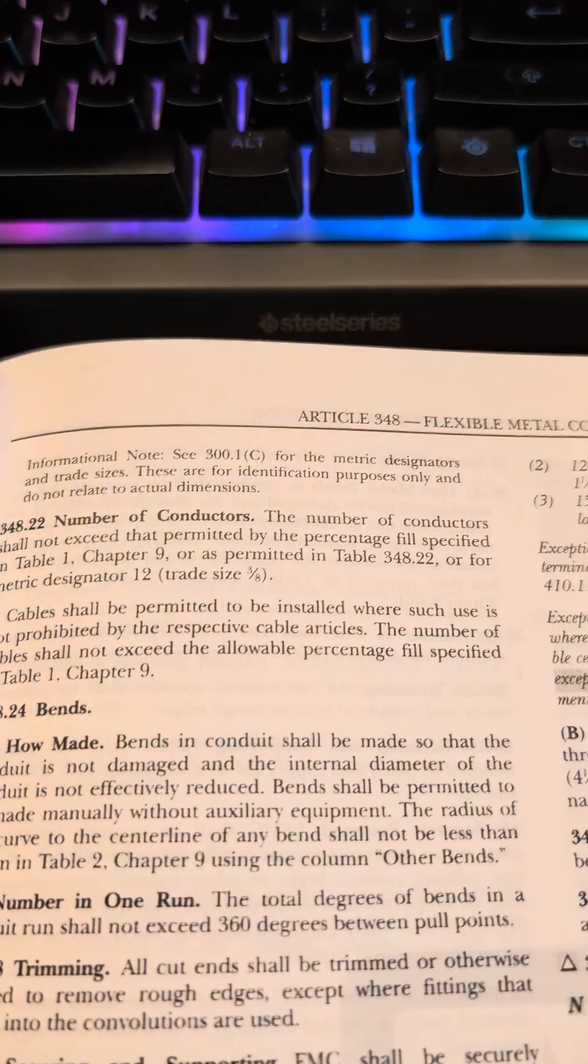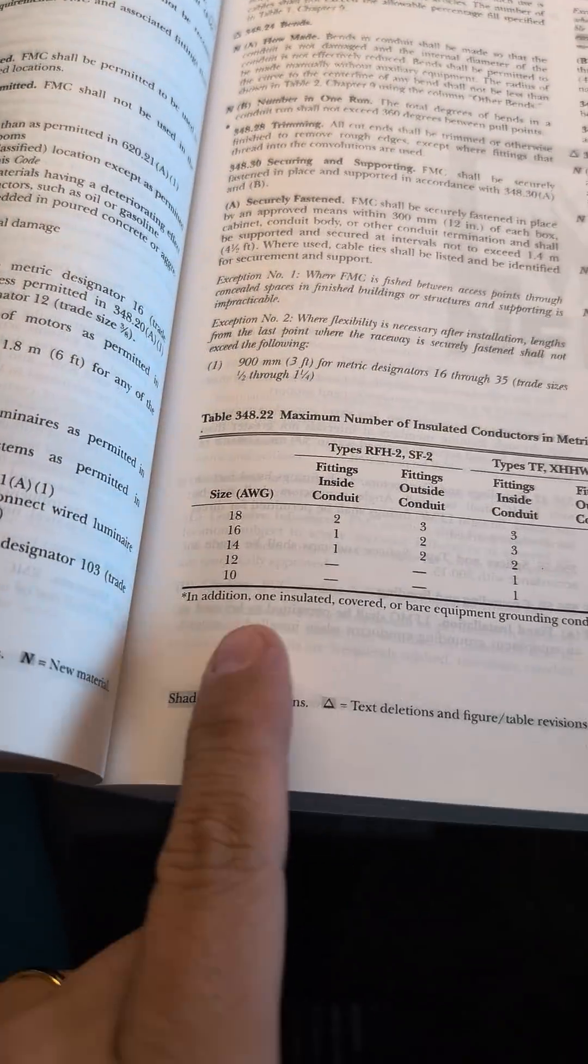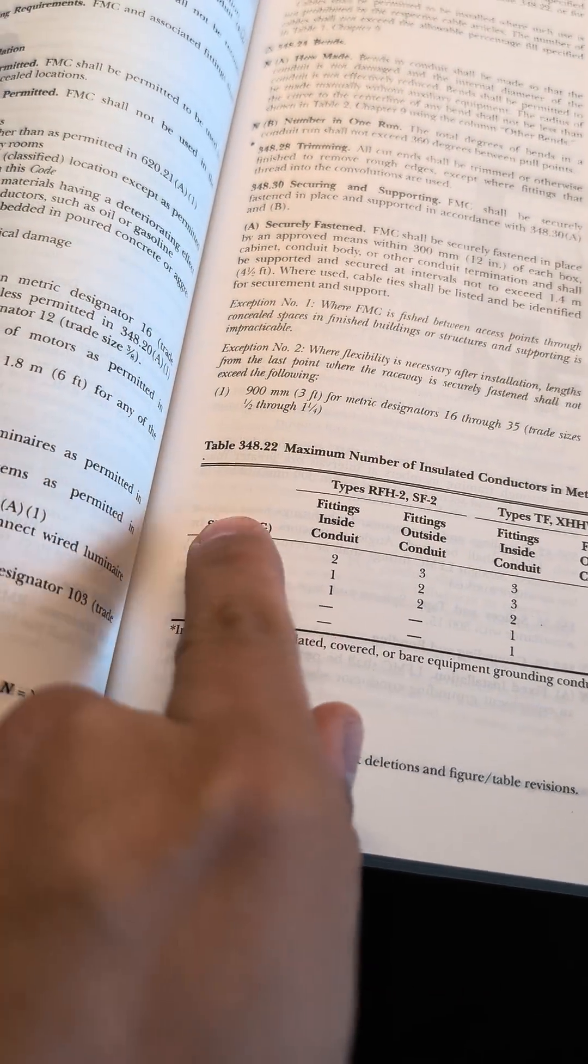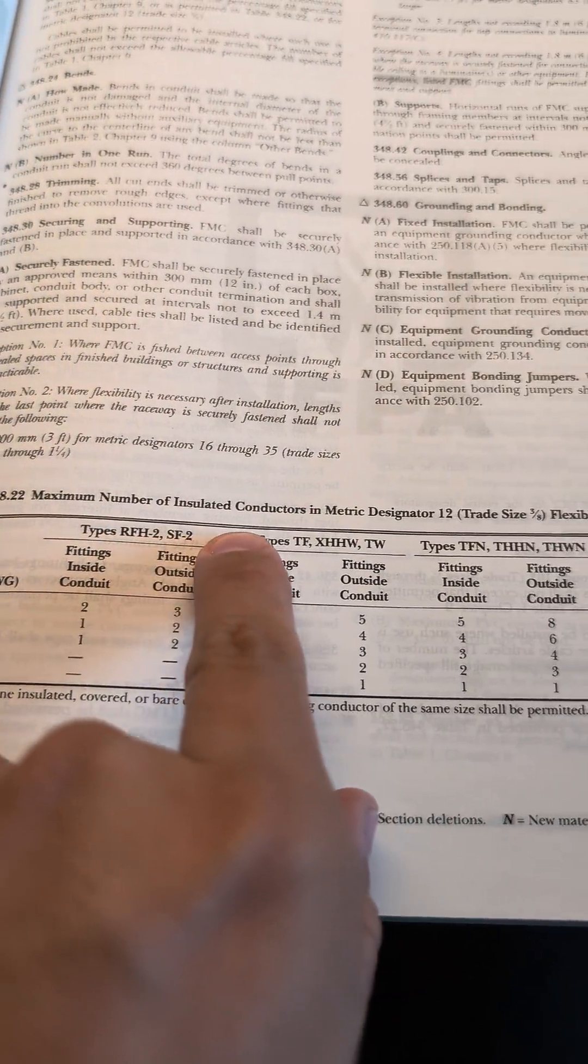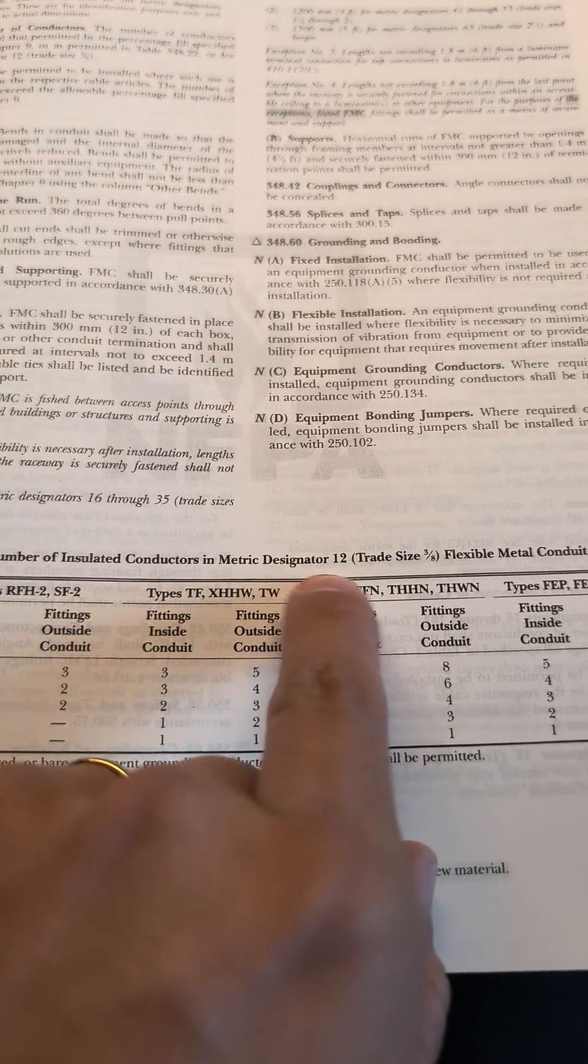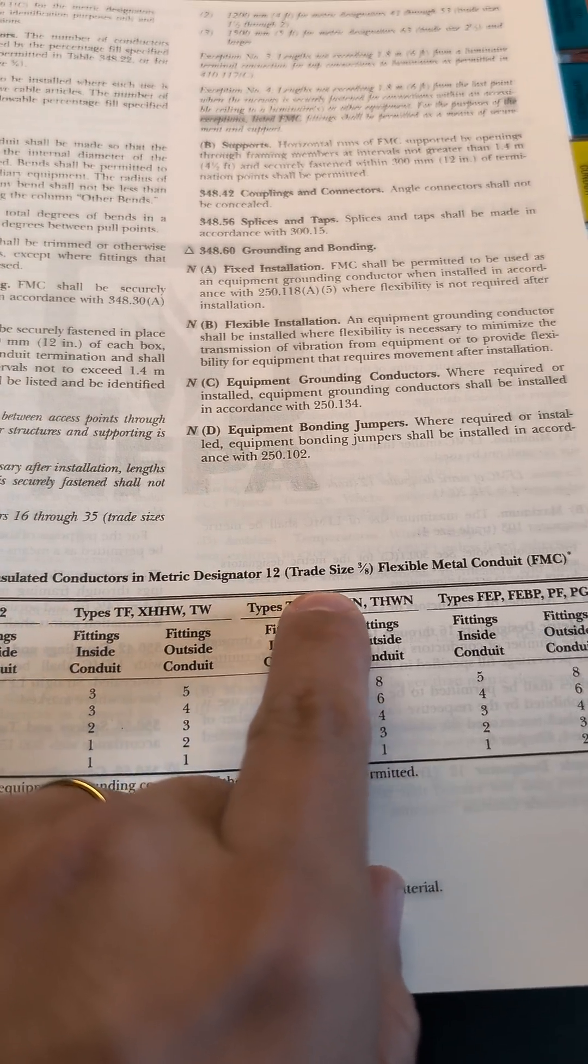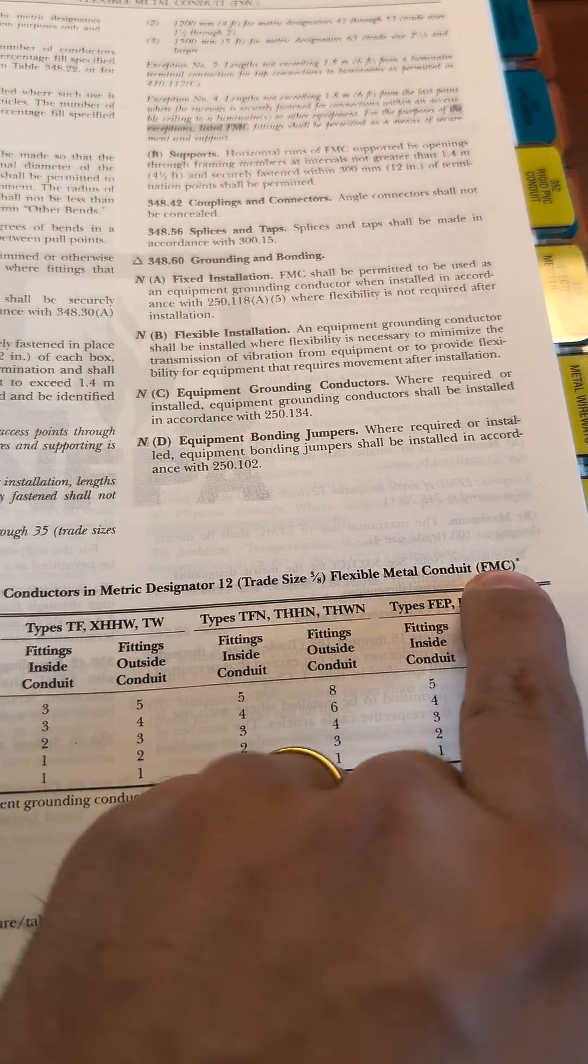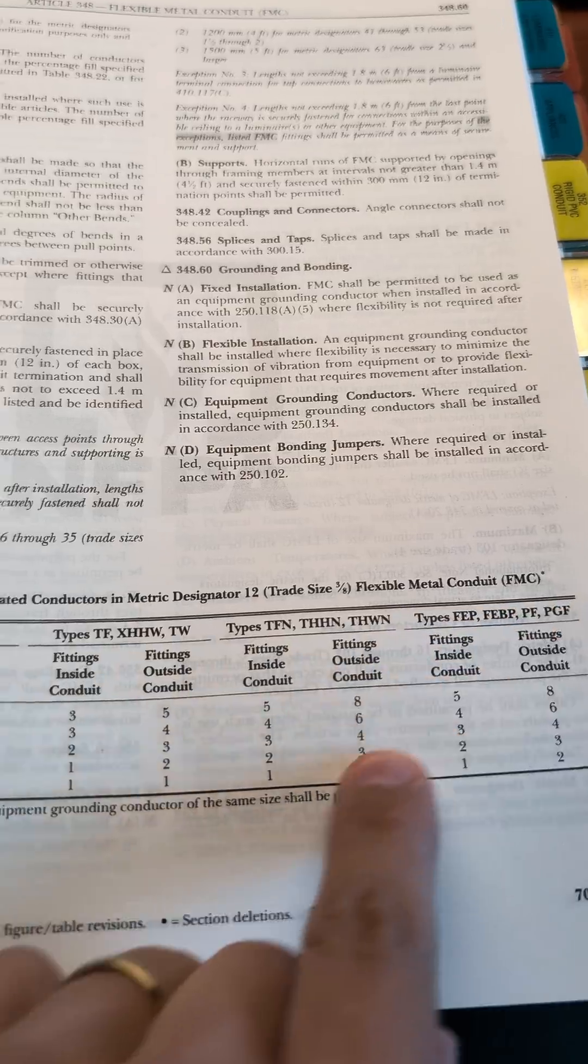Let's take a look at that table it's referencing. 348.22 is here. The maximum number of conductors in metric designator 12, trade size 3/8, FMC. There's a little star there.